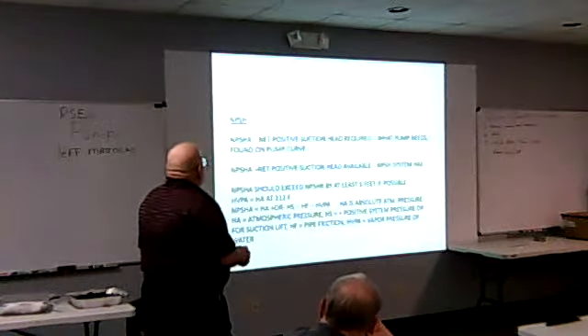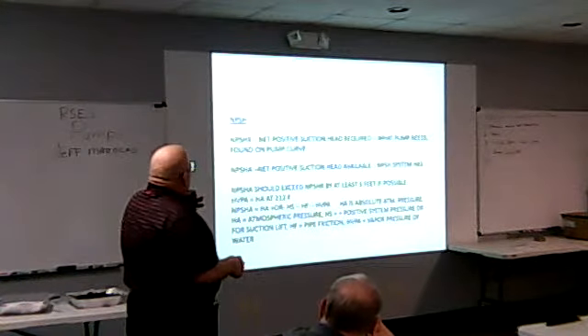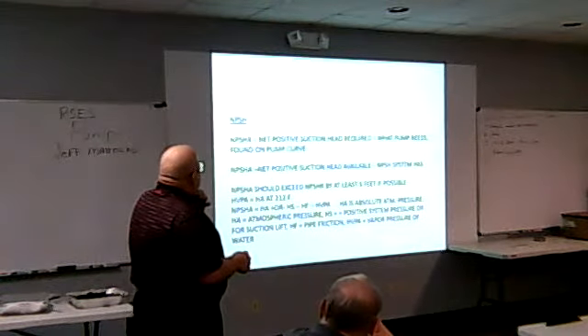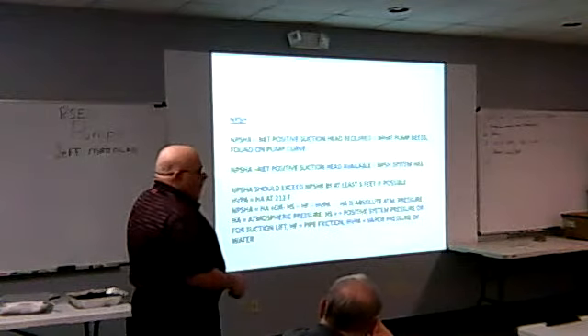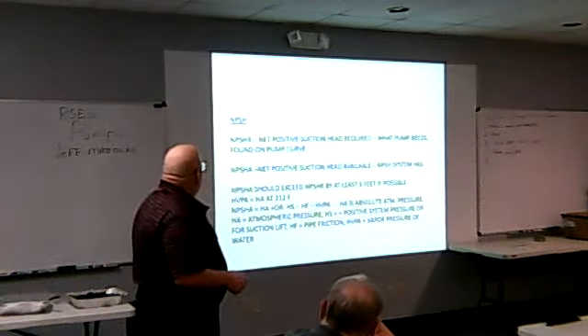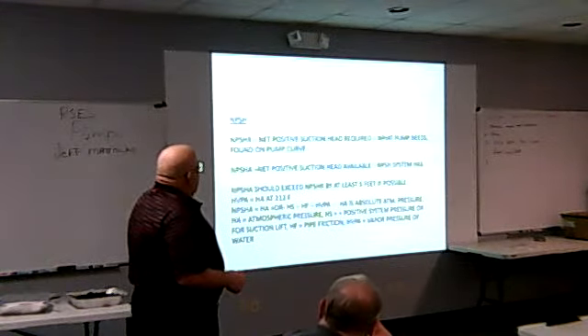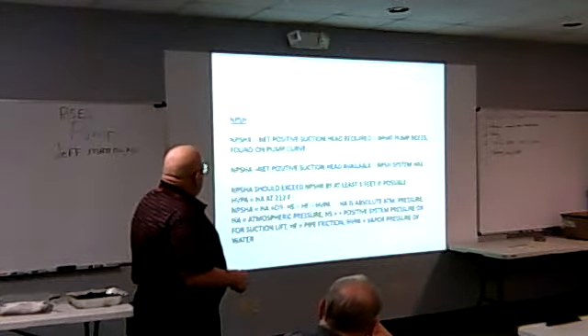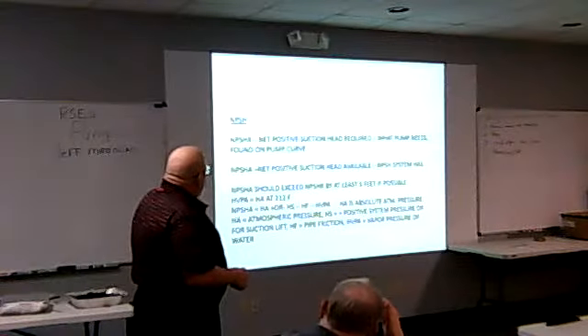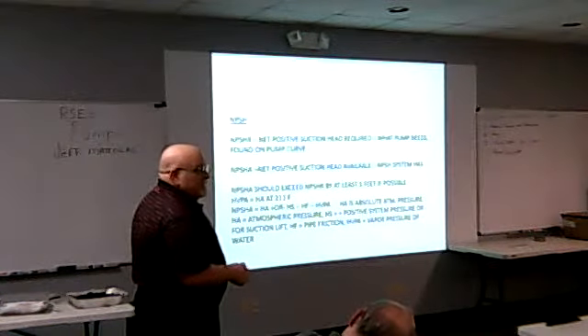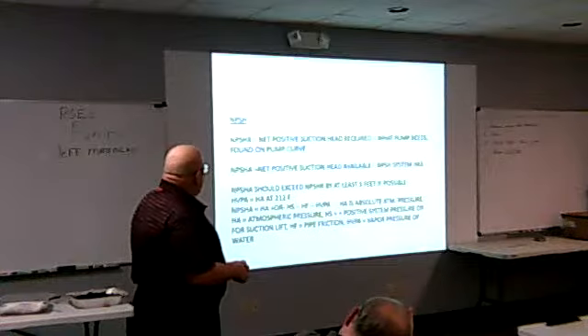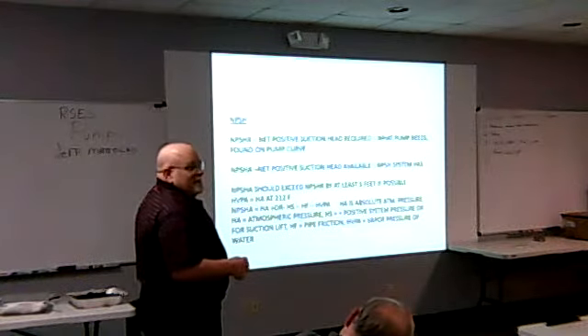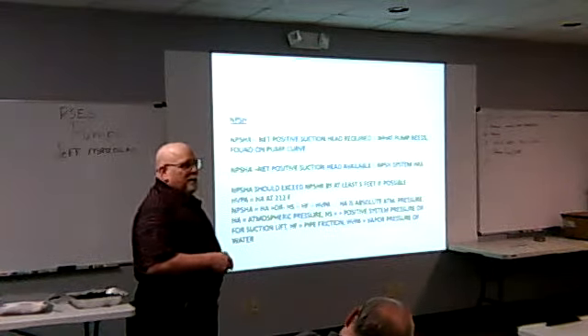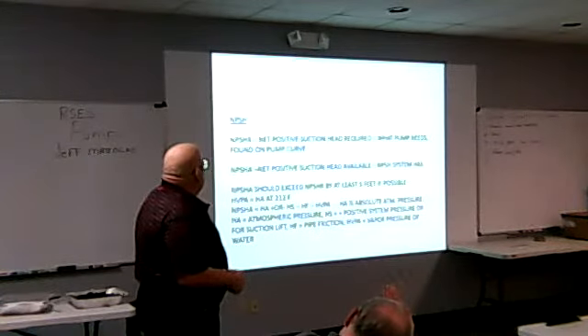Okay, we talked about these already. This is the net positive required. What's available has to exceed 5 feet. That keeps you out of trouble. That's 5 feet right here. You know, your vapor pressure. Remember I talked about that vapor pressure term, Hvp. At 212, it's 32 feet. I'm at 0. I lost all my first term. It's gone. Now I'm minus. That's why it's hard to pump it at full pressure.